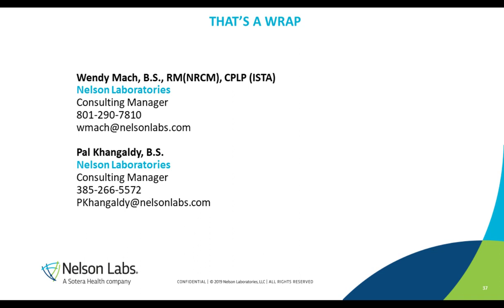We take your test samples and we expose them to the conditioning environment and the shipping hazards. An aliquot of those samples is removed, and we verify that there was no impact from the hazards or the conditioning on the devices. If everything is good, the samples that are left from the original testing, the shipping and climatic, then move into accelerated aging, and we pull sample sizes at interim time points throughout the stability period. And we evaluate them for new damage that could have occurred. This is a worst case and is very representative of what your product is seeing. Hopefully that clears it up a little bit more.